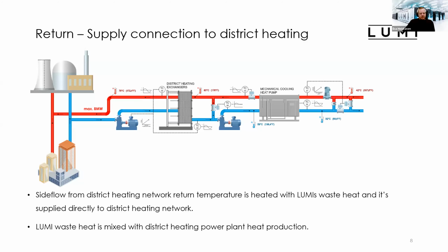We have two ways to provide district heating for the city of Kajaani. So there's return and supply connection to the district heating. Basically we are running this 80 degrees Celsius liquid from our heat pumps to these two heat exchangers. In this connection type, we are supplying it directly to the district heating network, which goes in the city of Kajaani. And we are taking a partial water flow from the city returning district heating network and preheating it, heating it again.